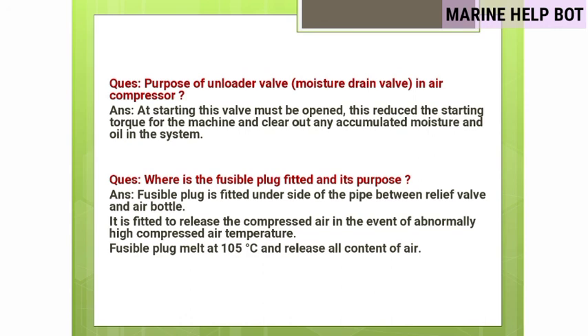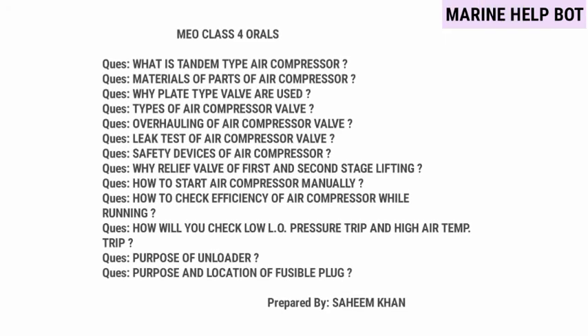Where is the fusible plug fitted and what is its purpose? The fusible plug is fitted on the underside of the pipe between the relief valve and the air bottle. It is fitted to release compressed air in the event of abnormally high compressed air temperature. The fusible plug melts at approximately 105°C and releases all the air content to atmosphere.